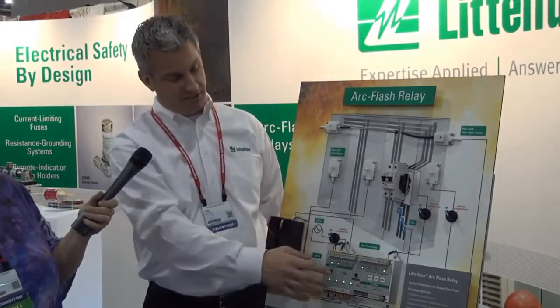Yeah, well, thank you, Teresa. We're highlighting our arc flash relay. Basically, in the most simplistic form, an arc flash relay is a light relay. It's looking for an overabundance of light. When it sees it, it takes that signal back into the relay and processes it, and then it sends out a signal to shut down power. A great example of that obviously is an arc flash, which emits a tremendous amount of light. So this will detect it, it sends it in here, and it processes it within 1 millisecond. Sends an output out to a circuit breaker to remove power. And again, it's extremely fast when it does that.